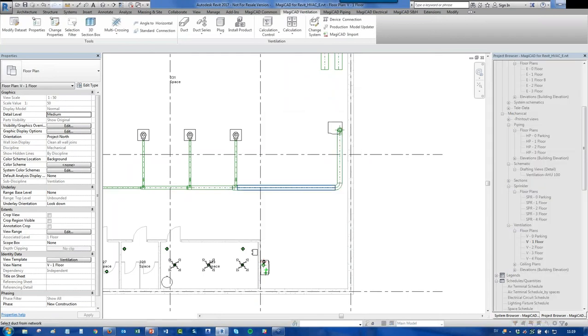So then I'm going to do the balancing again. In this case, I'm going to select balancing to pressure, to fan pressure. I click OK, and then you can see we have something totally different. Now we have about 101 instead of 60 Pa, and we have different adjustment values because that is actually what's going to happen in real life.